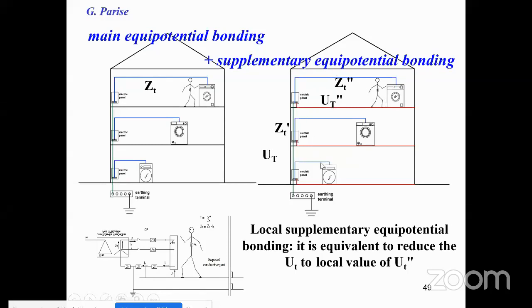and so this person touches a reduced voltage in comparison to the value. If there is a TN system, I don't have half the value of the voltage line to earth, but I reduce the part, and so it is more reduced. If I consider 100 volt, I have a part that can be 30 volt, 40 volt in comparison to 100 prospective value of the touch voltage.